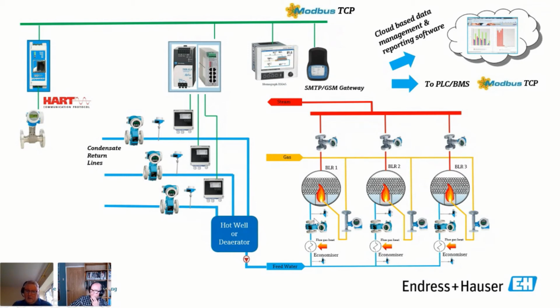Yeah, it's what we were saying before about these steam meters. There might be ten very useful multivariables in there, and yet people will still take a pulsed output from it, for either a kilogram or a kilowatt hour, when they could have about ten multivariables. But the only way to get all of the multivariables is through the digital protocol, something like HART, or Modbus TCP, Profinet, Ethernet IP, all these different protocols.